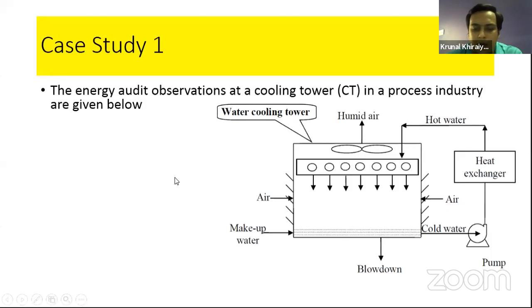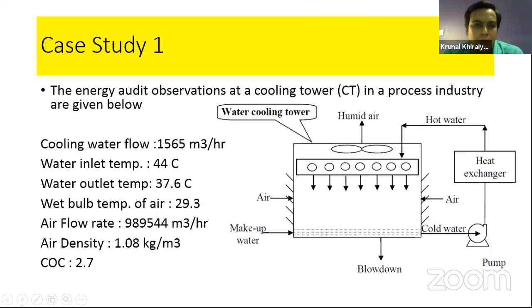So what are the data that we collected during the energy audit? Cooling water flow rate was measured with the help of ultrasonic flow measurement, that is 1565 meter cube per hour. Water inlet temperature is 44 degrees, which comes from here, the hot water. Water outlet temperature, supplied from the pump, is 37.6. Wet bulb temperature of air, meaning air temperature measured using the sling psychrometer, is 29.3. Air flow rate is 989544 meter cube per hour. The density of air is also an important parameter, 1.08 kg per meter cube.